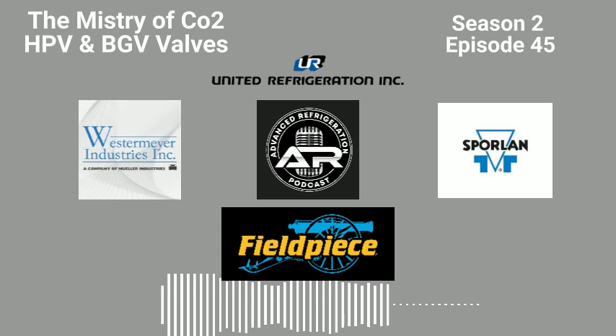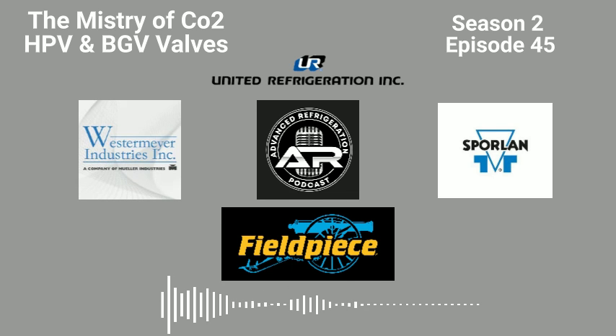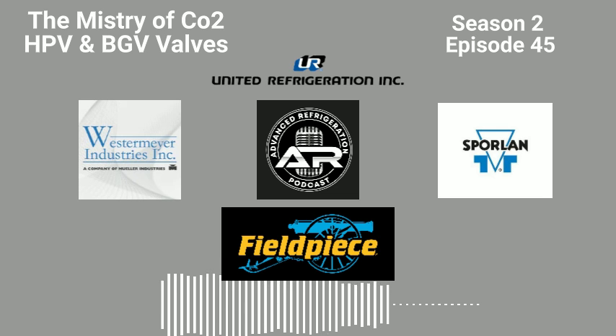Yeah, that's been a problem, and then all these racks outside on the roof. I absolutely despise racks on a roof because it's hot, it's cold, it's wet. No matter how good an electrical cabinet's sealed, it's still going to get wet, especially when you have exhaust fans sucking out of the cabinet and you're creating a vacuum in the cabinet. We've had a couple of these, and the manufacturers are mounting the controller on the door. This is the most important thing on the rack, and it's mounted on the inside of the electrical cabinet door, where the water is going to come in and drip down on it.